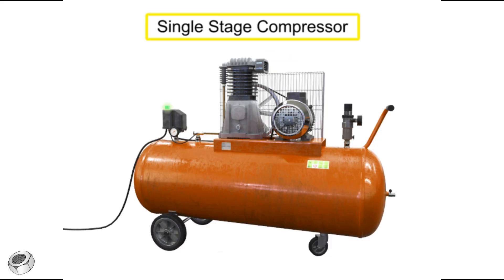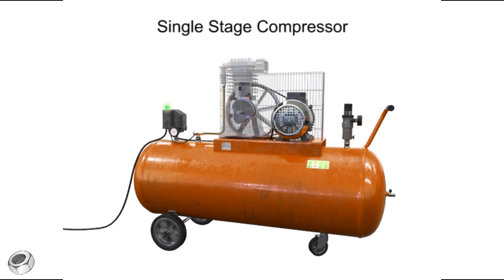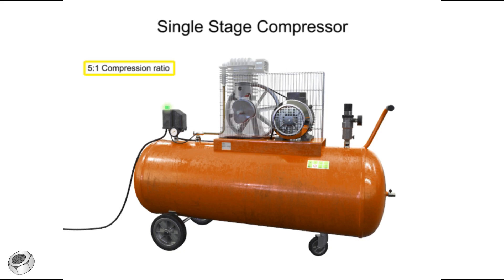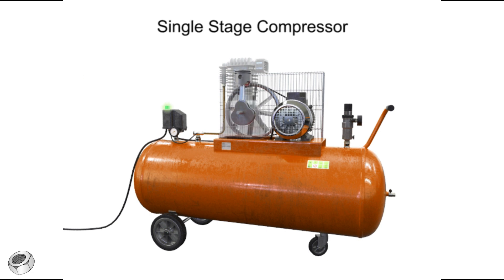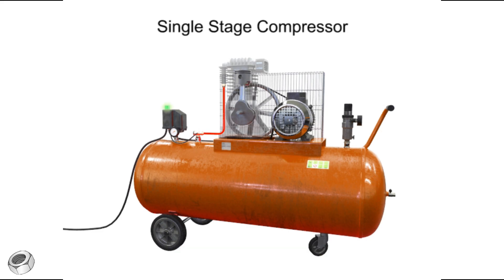This is a single stage compressor. It has only one piston and cylinder, and compresses the air in only one stage. A single stage compressor typically has a compression ratio of 5 to 1, with an output pressure of about 50 to 75 psi. As air is compressed, it becomes increasingly hot. If the air becomes too hot, not only is the compression cycle less efficient, but there is the hazard of an explosion if any hydrocarbon material, such as oil or lubricant, comes into contact with the overheated air.